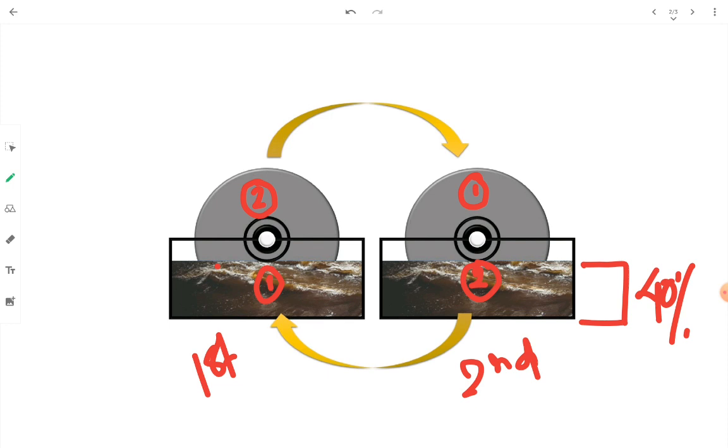Bacteria need two things for survival: food and oxygen. We are specifically talking about aerobic bacteria. The bacteria will obtain food when the disc is inside the wastewater. With each rotation, the disc carries some amount of organic matter or substrate on its surface, and at point 2 it is exposed to air, making oxygen available.